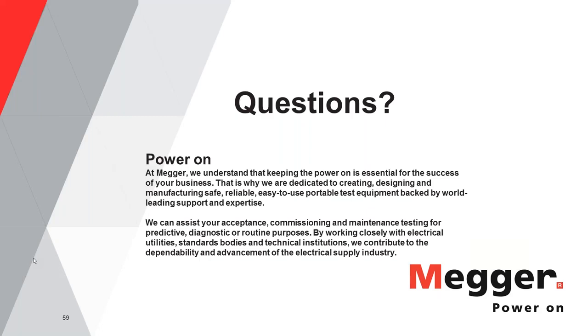have false operations. In regards to the frequency, that depends on the facility and the maintenance programs. I've seen testing programs every 2 years. I've seen also testing programs every 5 years, or in some situations every year. So it's more like an internal criteria, depending on the criticality of the loads and the systems that you have, and also on the resources.